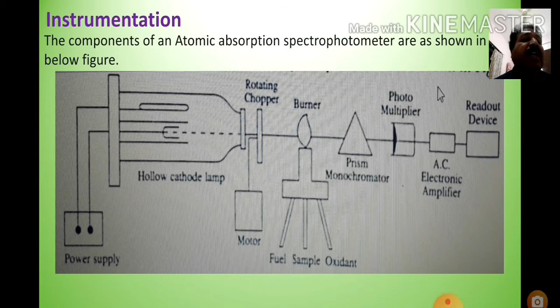Now let us see the instrumentation. The components of an atomic absorption spectrophotometer are as shown in the figure below. It includes the source of radiation, that is the hollow cathode lamp, rotating chopper, burner, prism monochromator, then detectors, that is photomultiplier tube, AC electronic amplifier and readout device.